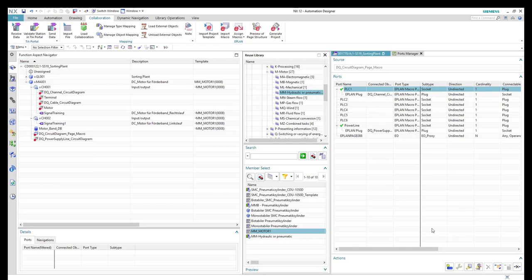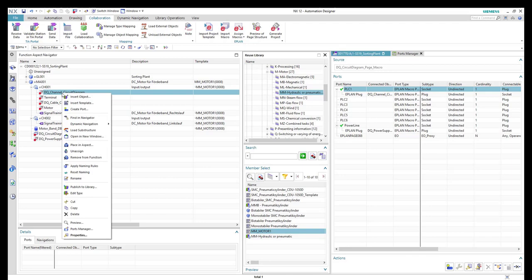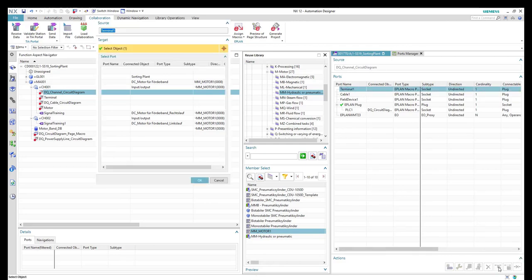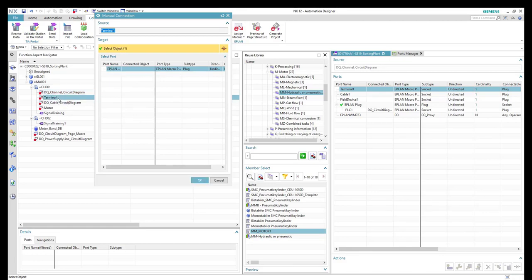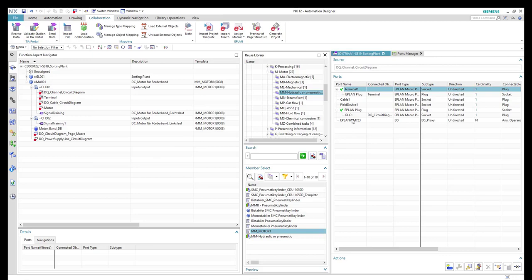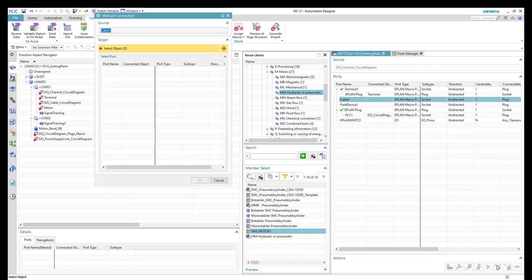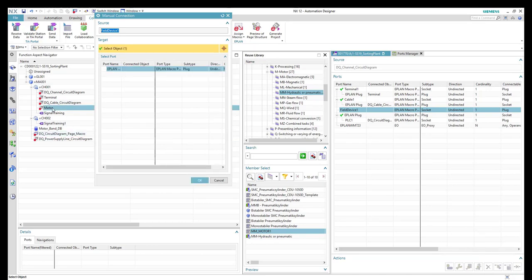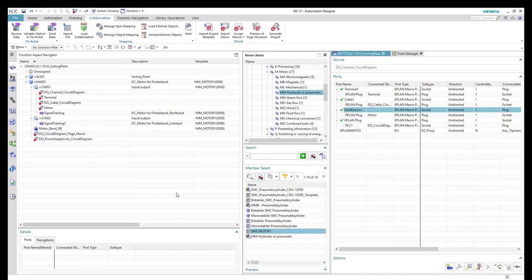Now we want to connect the digital output channel circuit diagram macro to the other macros. We open the ports manager and see all connections and sockets. We do a manual connection and select the terminal macro for the terminal socket. We then do the same for the cable and the field device, which is a sensor. Now we have a plug assigned to each socket and all connections are established.